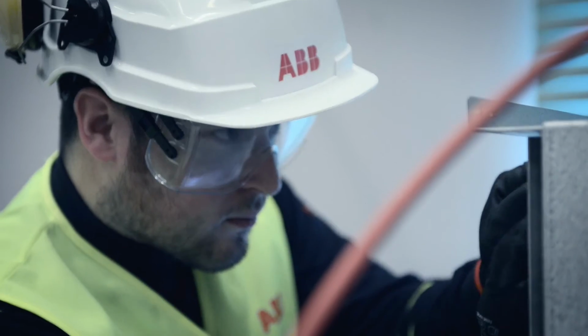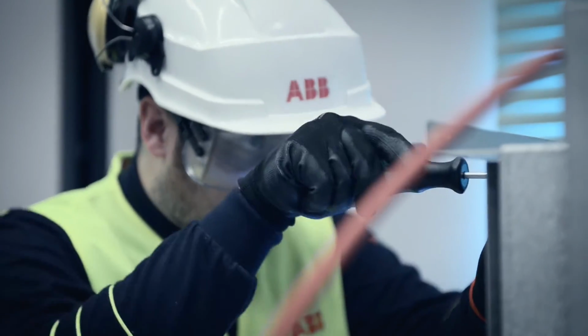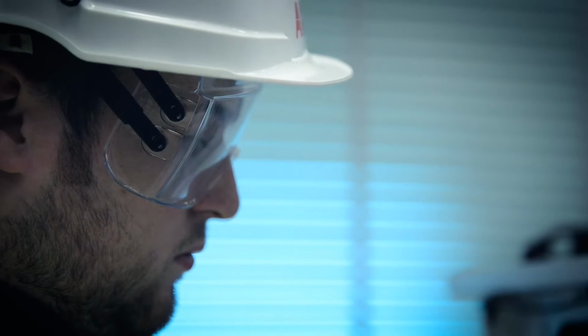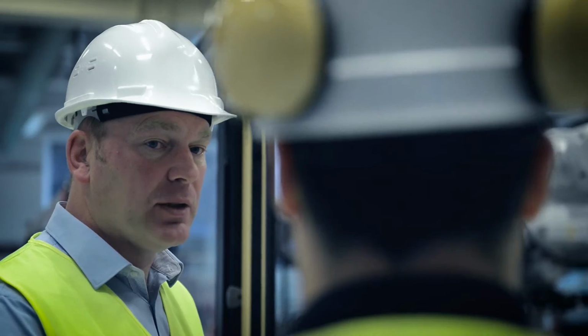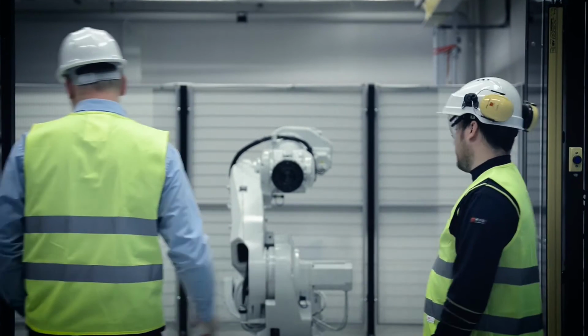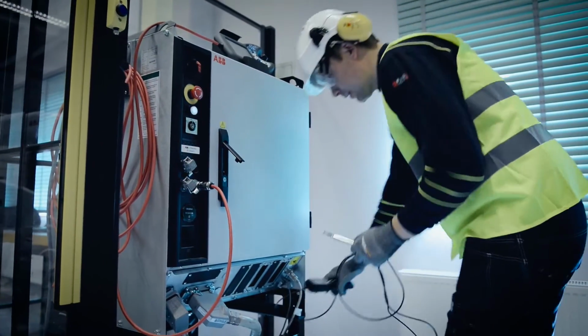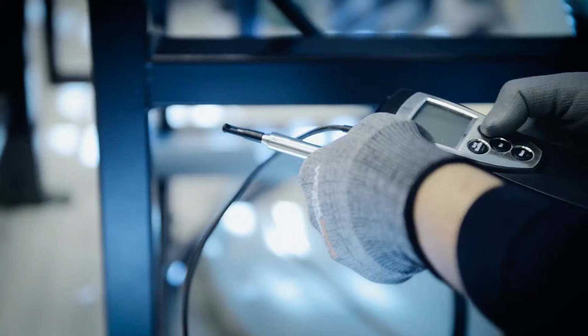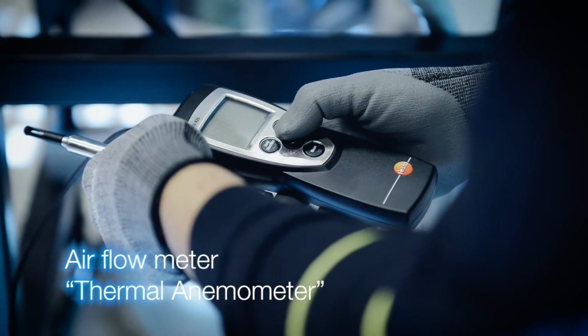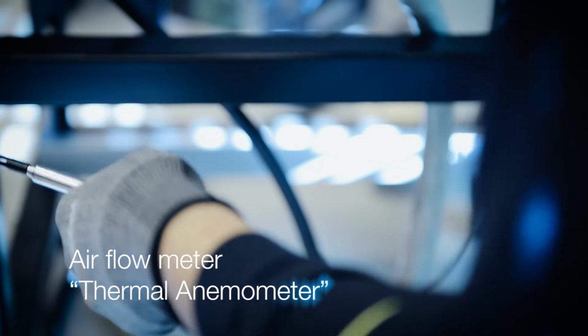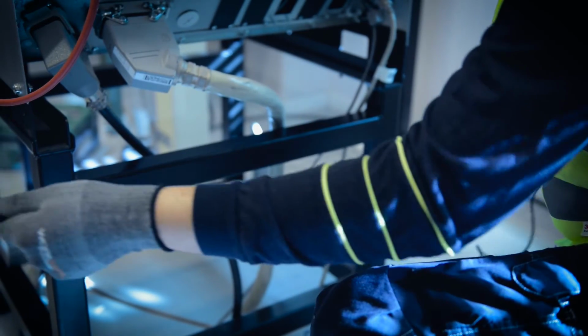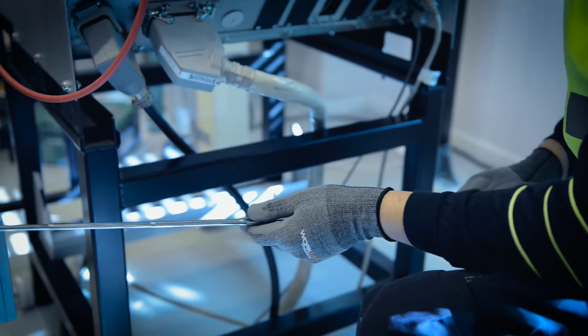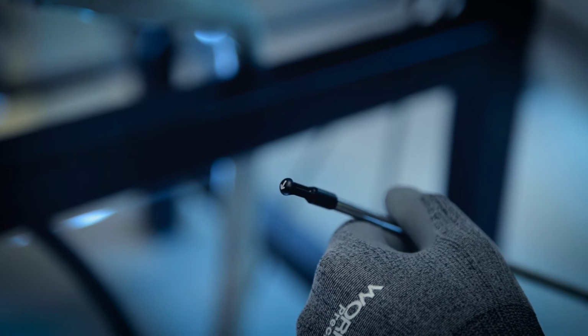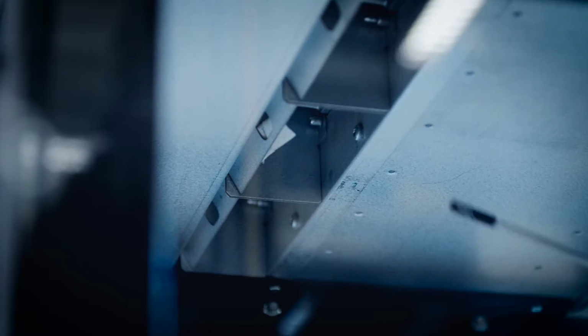The condition and airflow of the fans on the controller also needs to be inspected and rectified if required to ensure adequate cooling is provided to drive modules. Particularly more so if the controller is working in a high temperature or dirty environment. The inspection activities are performed using tools specifically designed to suit the purpose. These include airflow meters, so-called thermal anemometers, to measure the airflow of the controller cooling fans while recording the flow rates in the checklist. A traffic light indication process is used to determine the correct working range for the environment and the ambient temperature.